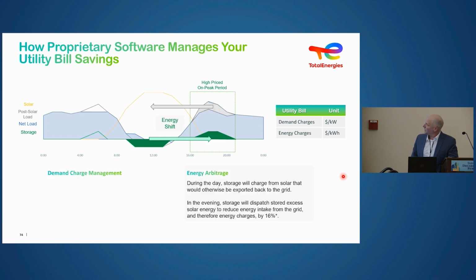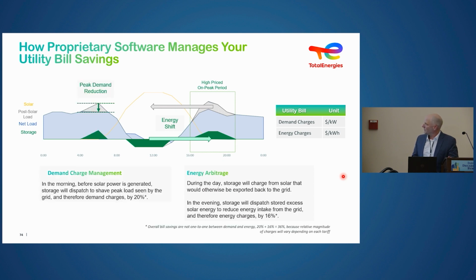The other way is with energy arbitrage. The green in the middle that is negative is where the solar is exporting, and we're able to dump some of that into the battery, charging it. Then we discharge it, on the right, during peak times when energy prices are significantly higher, between 4 and 9 o'clock. That energy arbitrage results in about a 16% increase in savings for this particular example, with about a 20% increase with the demand offsets. So you're adding some really significant economic benefit to the project with solar and storage combined.